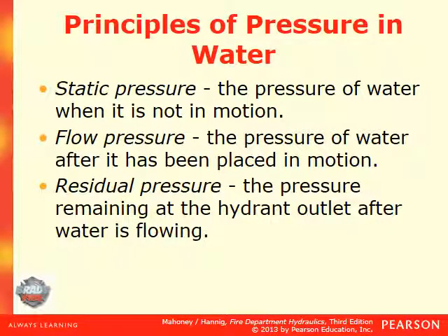Okay, more key terms. Static pressure is the pressure of water when it is not in motion. Flow pressure is the pressure of water after it has been placed in motion. And residual pressure is the pressure remaining at the hydrant outlet after water is flowing.